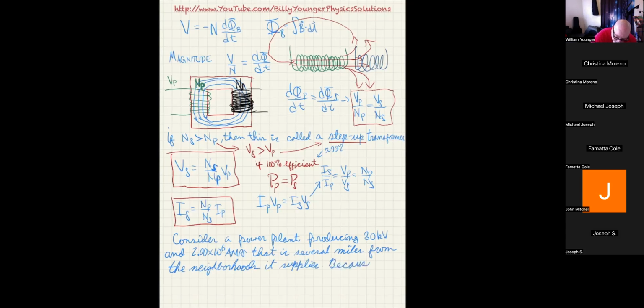Because of that distance, R is equal to, on the order of, let's say, 10.0 ohms. So these are pretty good sized wires. You can't make but so big a wire, so you actually have to have braided wire, but ultimately the diameter could be like 2 inches. With that large of an opening, you get a fairly low resistance, where literally miles might only be about 10 ohms total for just the wire. They mostly use aluminum for long distances because it's a lot cheaper than copper and only moderately less conductive, so they use aluminum a lot.